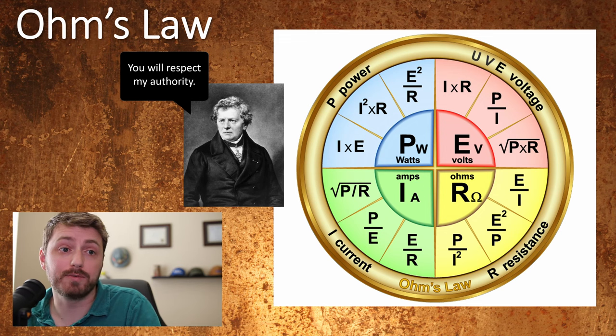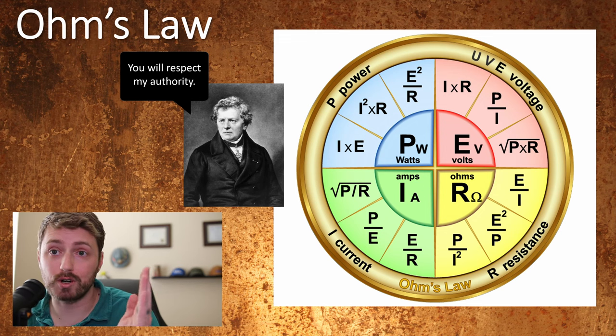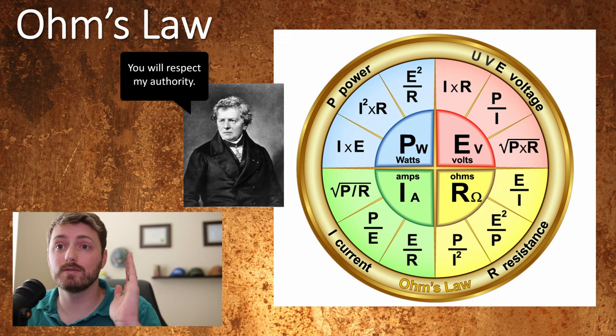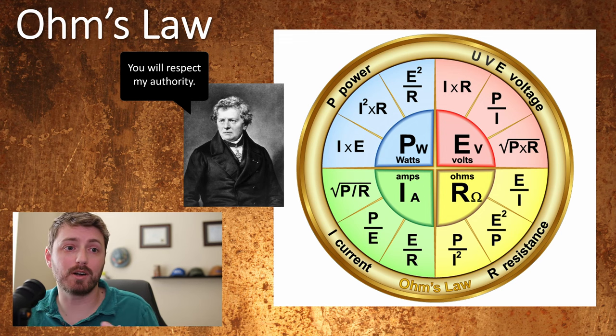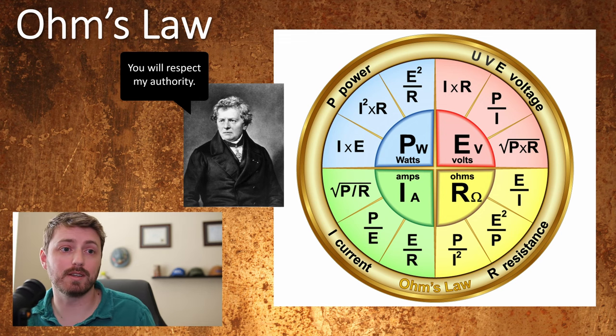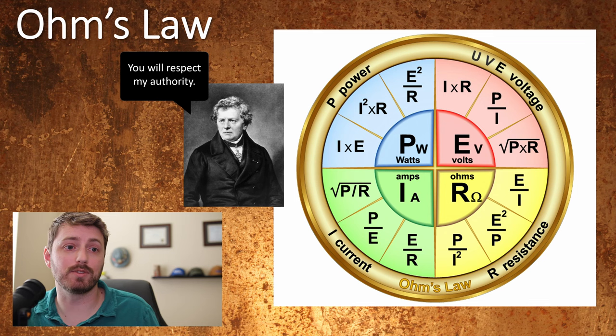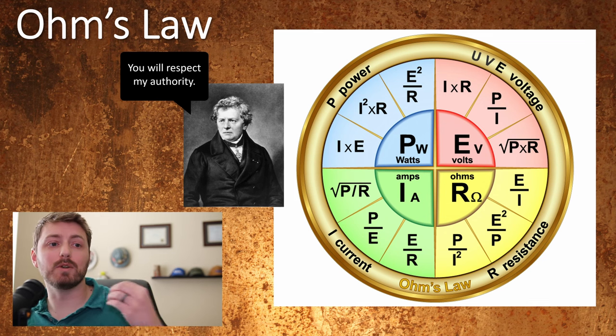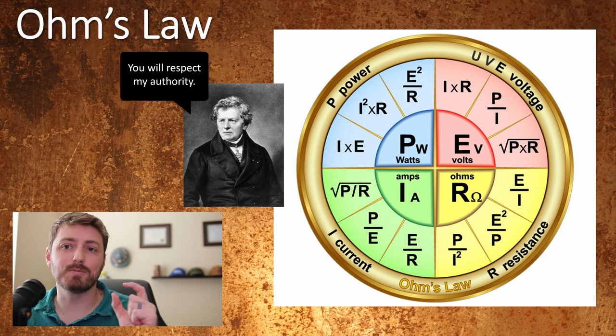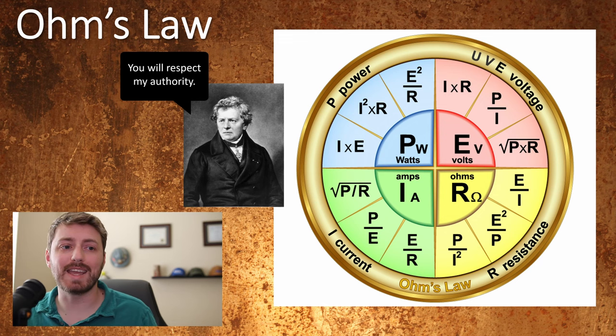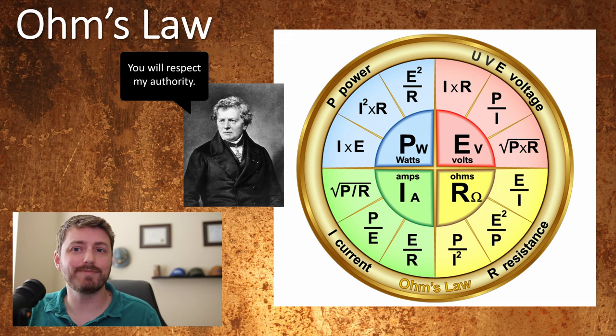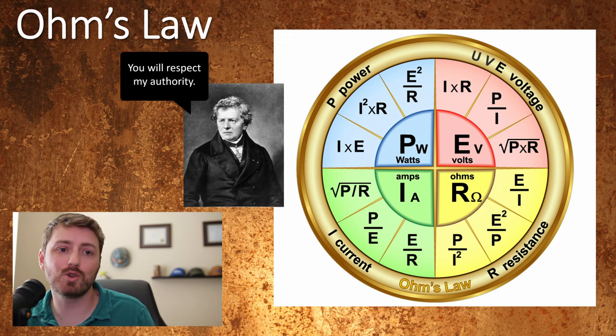From Ohm's law we know that power dissipation is equal to I² × R — current squared times resistance. As we make breakers larger and larger to handle more and more current, sometimes in the thousands or tens of thousands of amps, we really need to have the smallest R or resistance value as possible. Intentionally putting a heater coil in the middle of a breaker isn't the smartest choice on the bigger end.